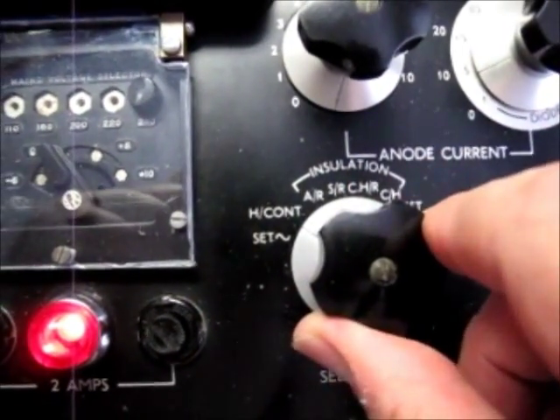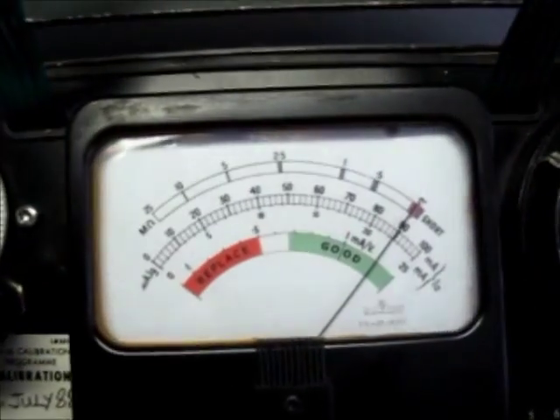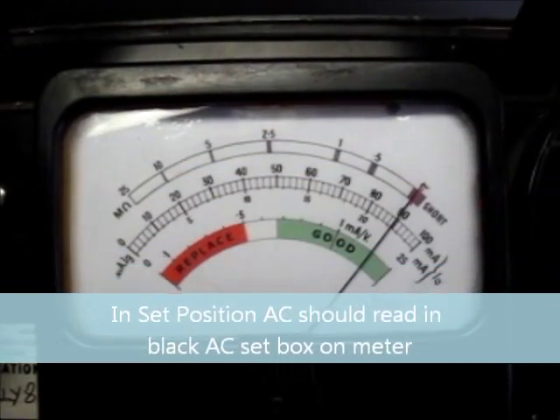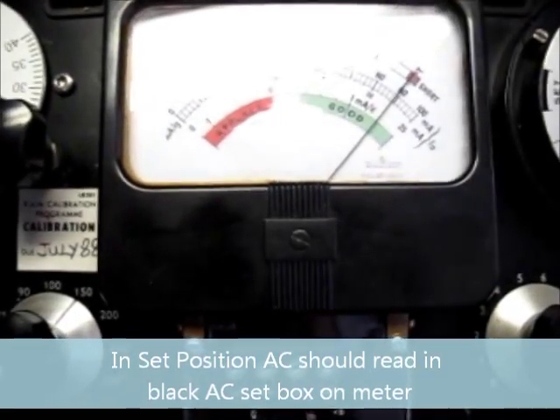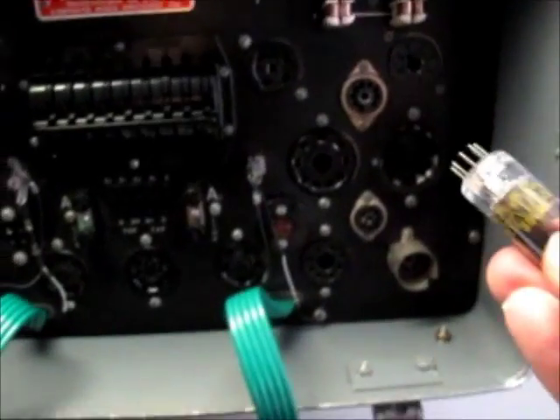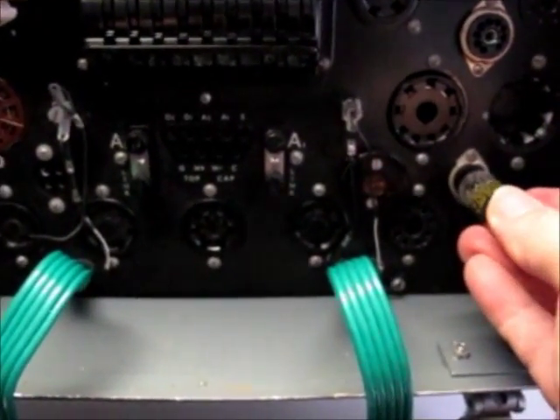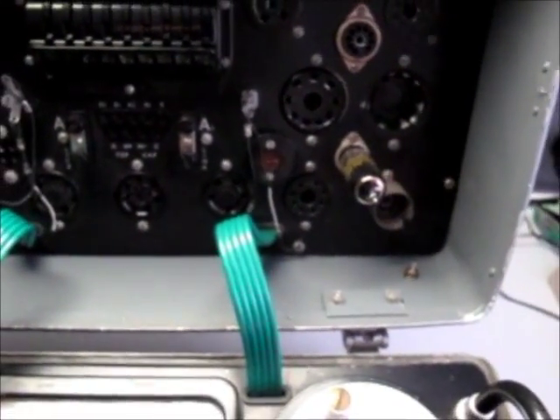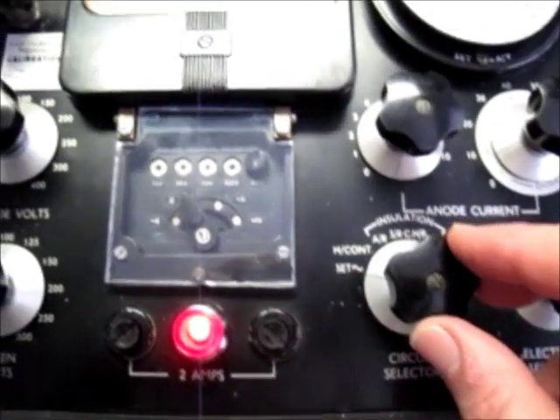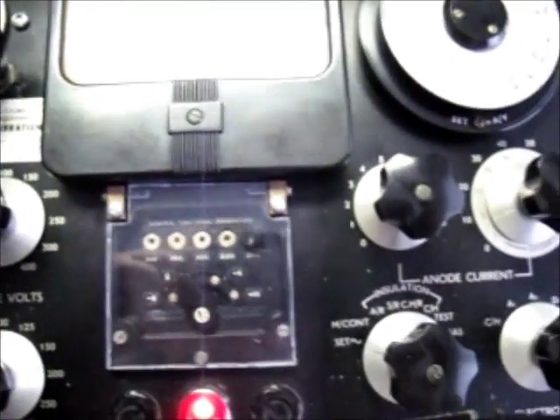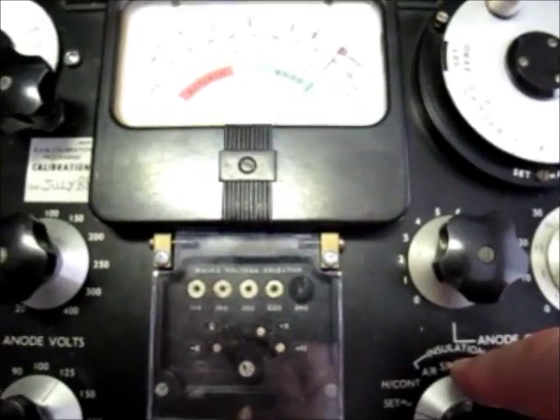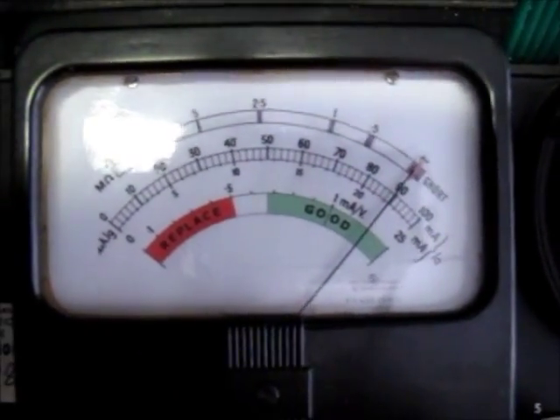We're in currently the heater continuity test. I'll just set the meter across to make sure she's meeting where she should be, and the meter is sitting where it should sit. Now the next thing we'll do is actually plug the valve in. So we'll take the valve, we'll find the requisite socket, which is the lower socket, and plug it in. The valve is in. Now at this stage the heaters aren't actually energized. We'll come back down to the settings, and we'll try and move some light out of the way here so we can see a bit better. And we'll now go to heater continuity, and we're supposed to make sure that the line is still set near the short mark, which it in fact is.